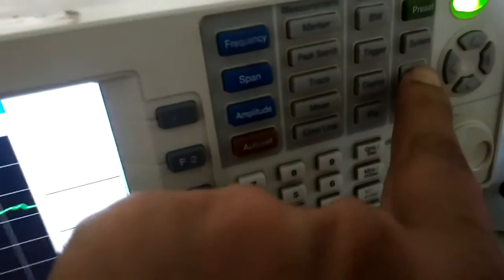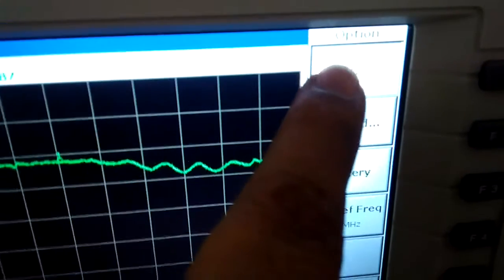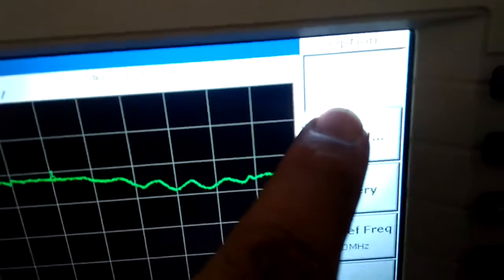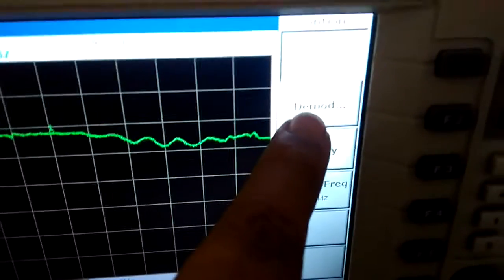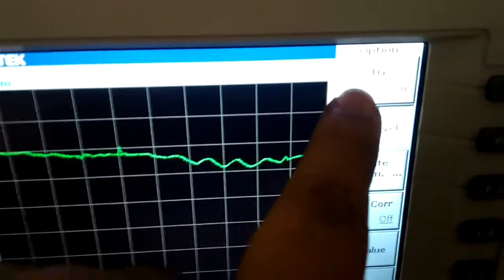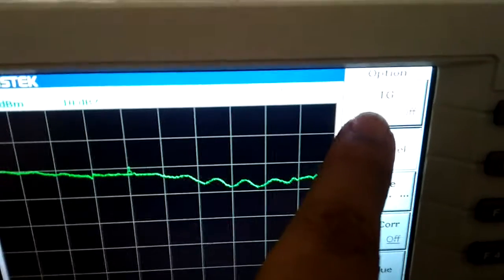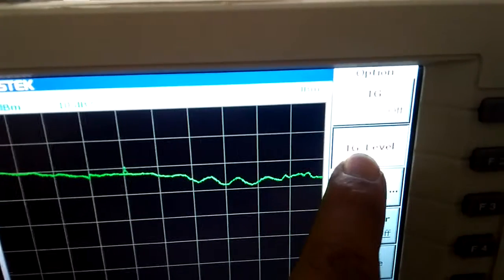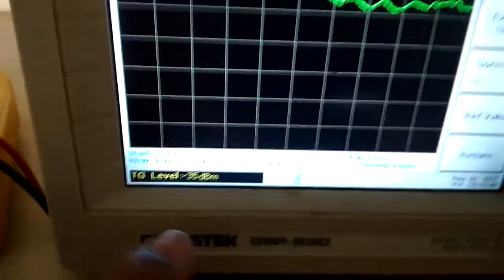And I am turning on this tracking generator with the help of this option button. If you go in the option button, then there is a setting called tracking generator setting.